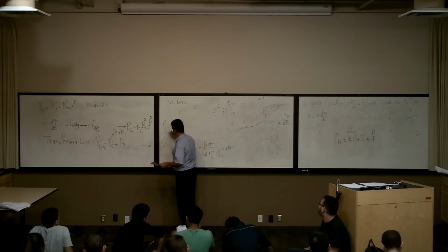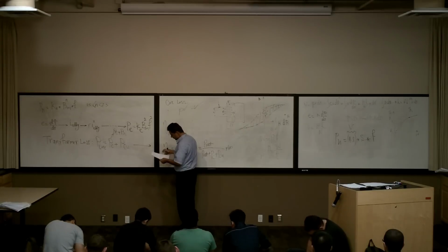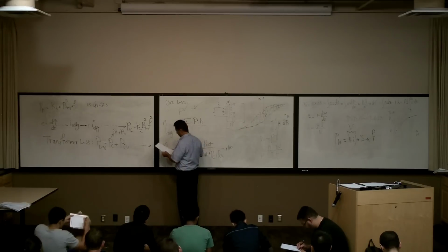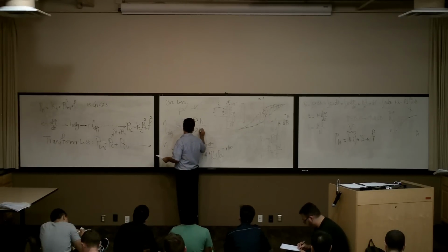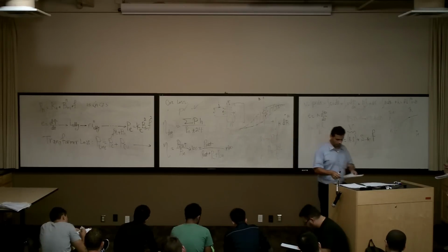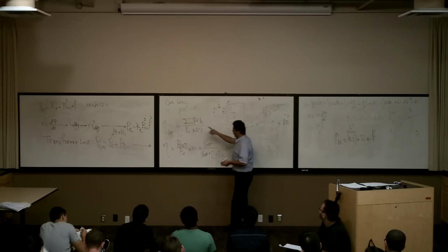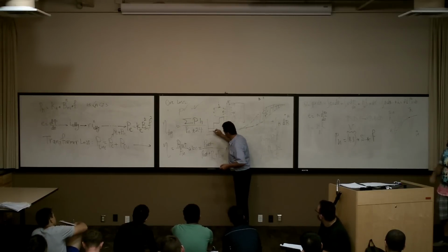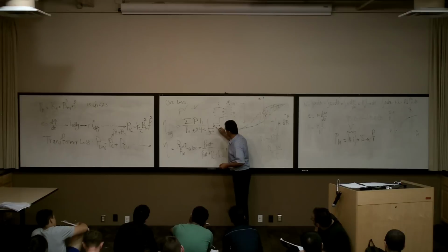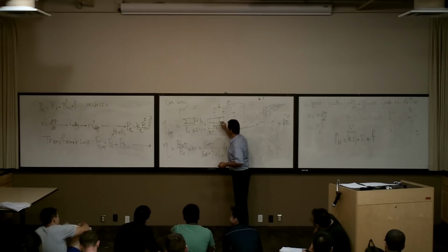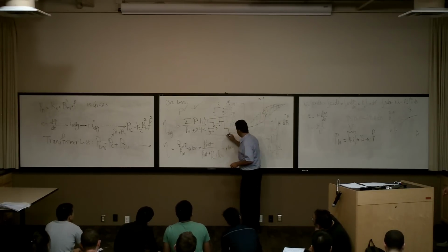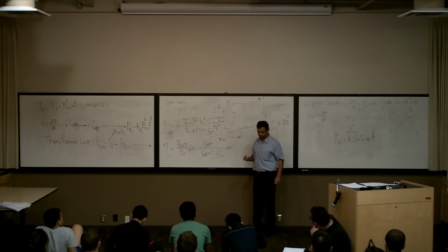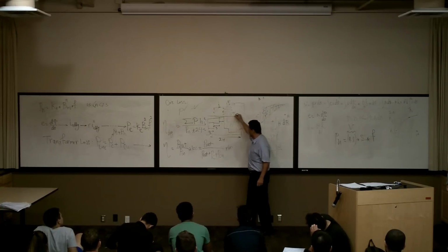Daily efficiency, over the day, is going to be sigma P times H divided by P_n times 24. Keep this equation because I'm going to solve the example. I'll say one more time. What is PH? Let's say this is a transformer load. For example, 2 hours you have 2 kW, 3 hours you have 6 kW, 1 hour you have 8 kW, right? And this is over 24 hours.